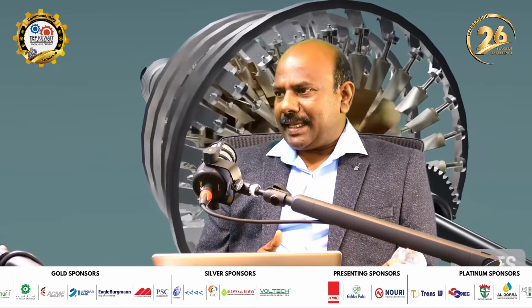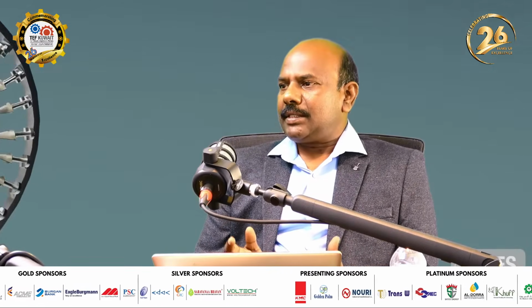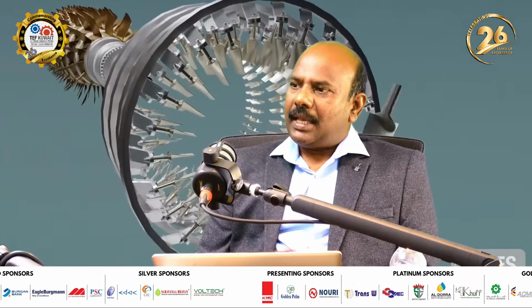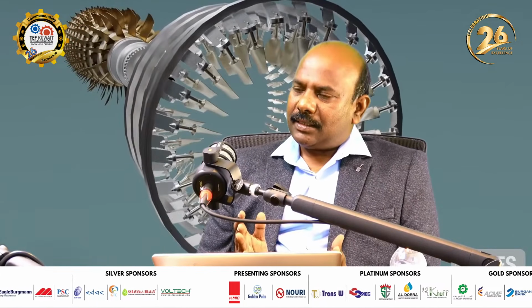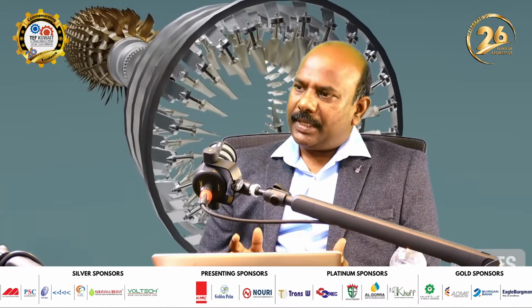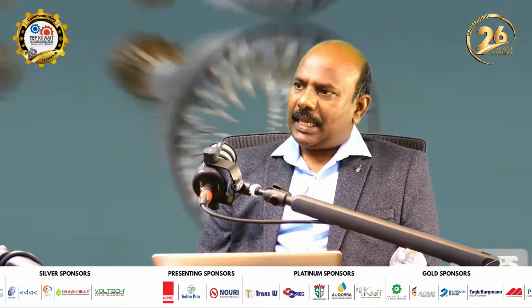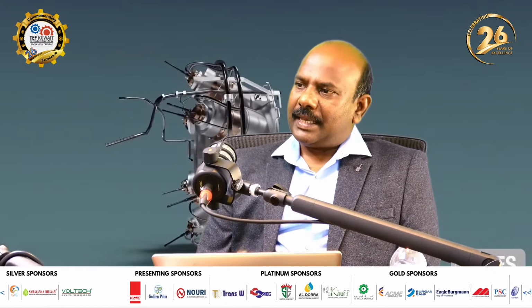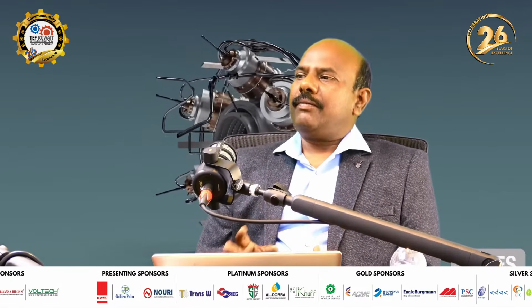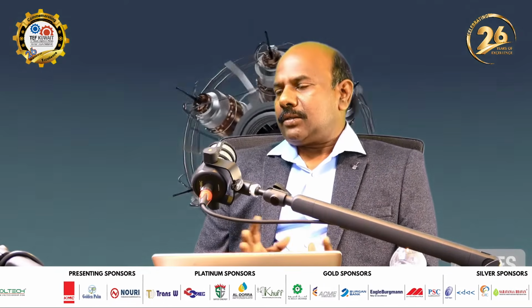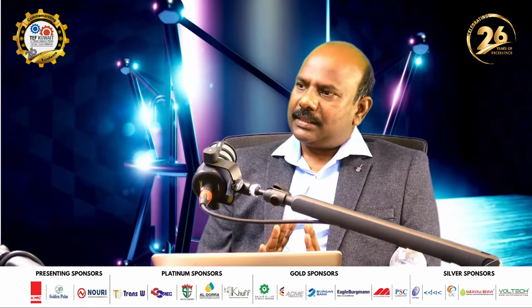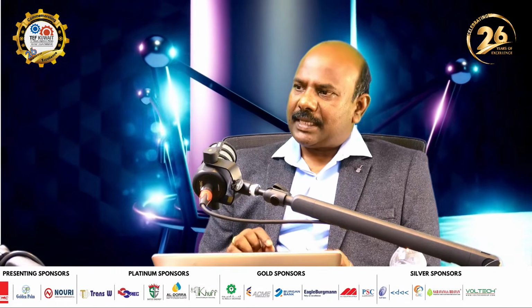For example, in a gas turbine, combustion parts replacement has to be done every 12,000 hours, hot gas parts have to be replaced every 24,000 firing hours, and the gas turbine definitely has to be overhauled after 48,000 running hours. So for such equipment, there is no other way - preventive maintenance has to be done.